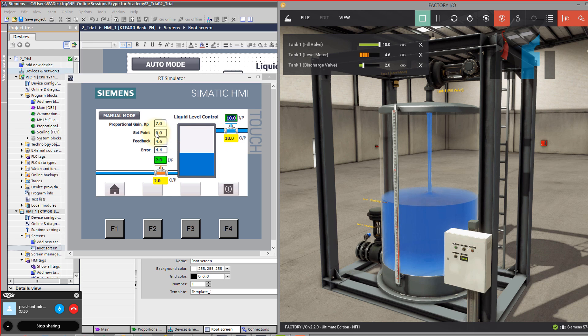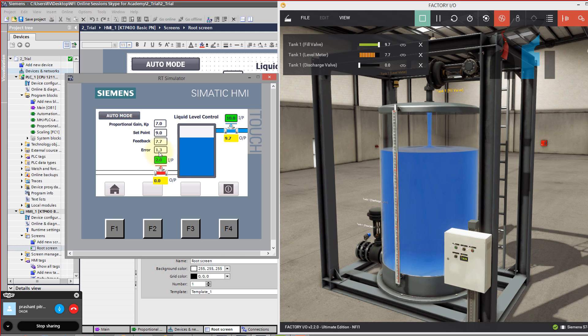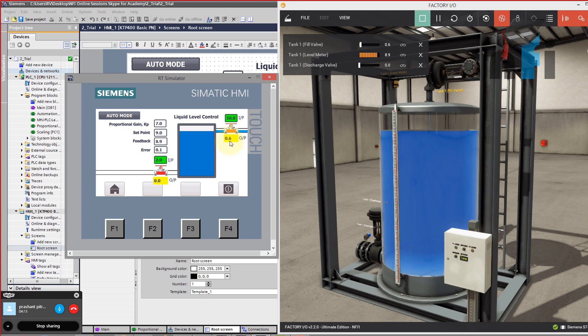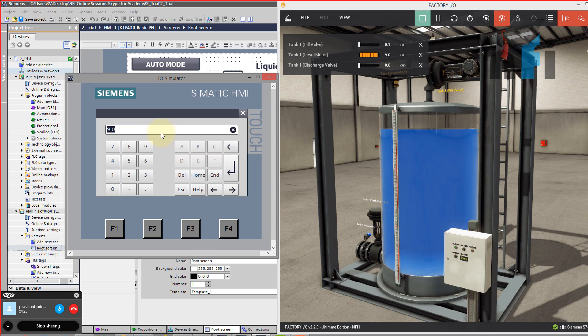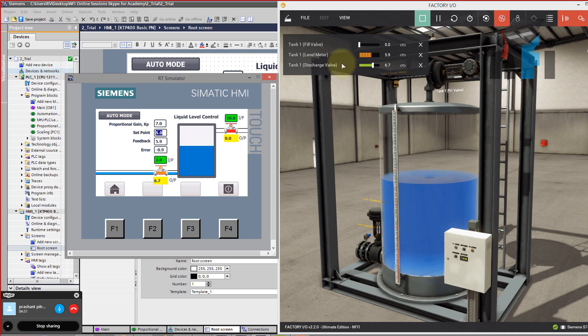In manual mode we are not controlling the level like in the last lesson where we gave a set point to control the level. But if I go to auto mode by clicking this button, it will follow the set point and here you have the error. This will stop when the value goes to 9 — you can see it's going to 9 and the valve is getting closed automatically. If I change the set point to 50%, the filling valve is closed, draining is on, and the level is decreasing.